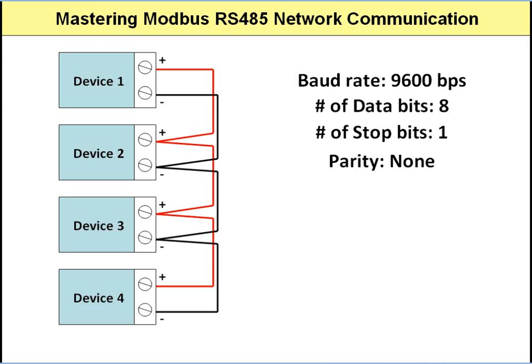The main thing from this lecture is that you understand these 4 configuration parameters, understand what they mean, but much more importantly, understand the fact that whatever settings you use for the RS485 network, those same port settings must be on every single device. They must match, they must be identical, otherwise there will be no communication on the network. Great.